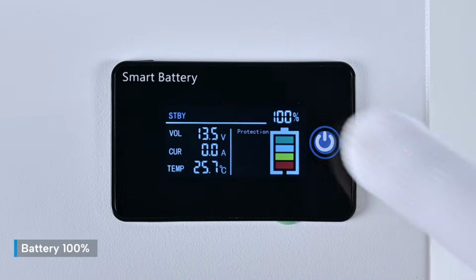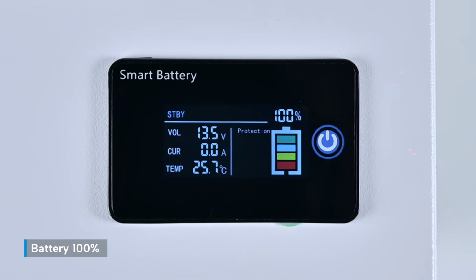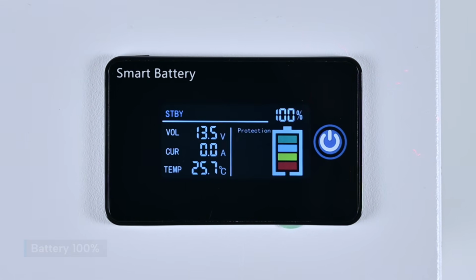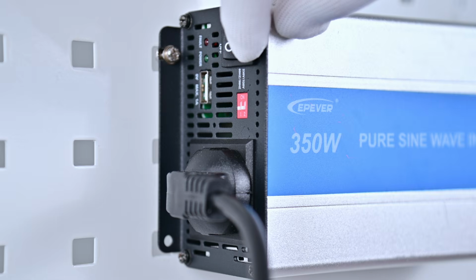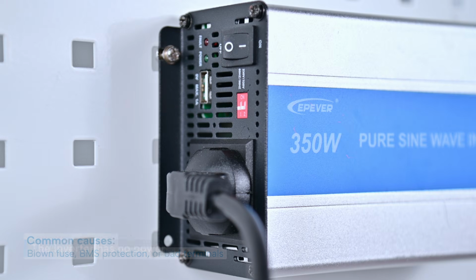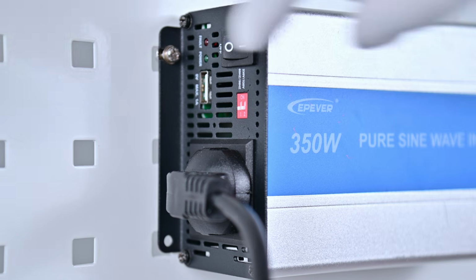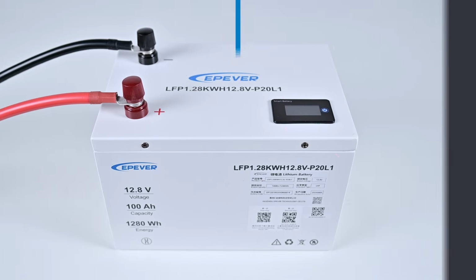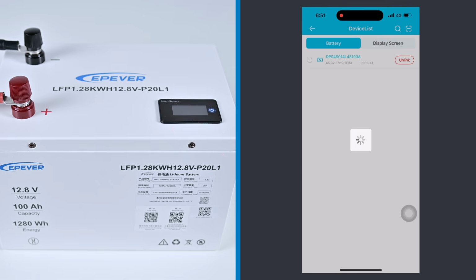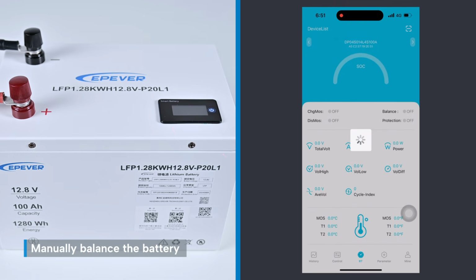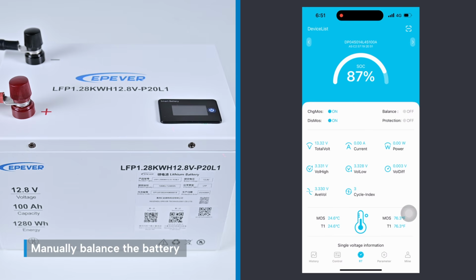Fault 4, battery not discharging. Battery shows full, but no output. The inverter shuts down or gives a low voltage alert. Could be a blown fuse, BMS protection, or bad terminals. Please check the connections and manually balance the batteries using the official app. Replace the fuse if necessary, and then restart the inverter to test the output.